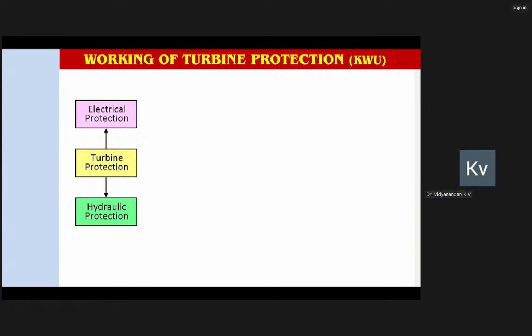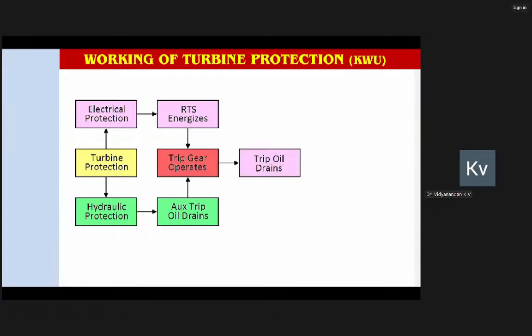Usually, it is divided into two groups. One is electrical and the other is hydro-mechanical or, in certain cases, only hydraulic. In case of electrical, the end operation is the energization of the remote trip solenoid. Whereas in hydraulic protection, the respective oil, in a KWU turbine, we call the auxiliary trip oil. That oil will be drained. So whether the RTS energizes or the auxiliary trip oil drains, ultimately the trip gear operates, and trip gear operation means trip oil will drain, and draining of the trip oil means stop and control valves will close. This is the typical KWU turbine.